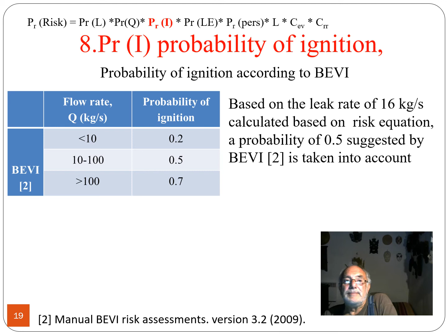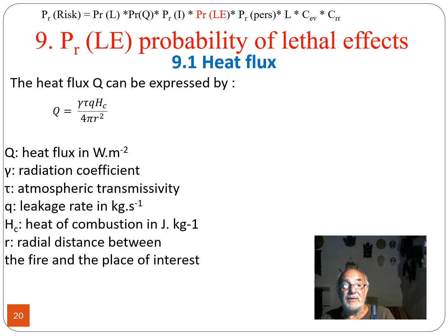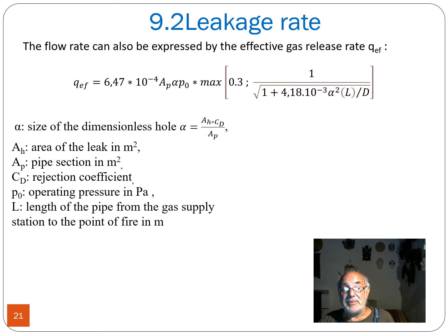The probability of lethal effect can be computed for two situations: heat flux or explosion. The heat flux, capital Q, can be expressed by this formula, where gamma is the radiation coefficient, tau the atmospheric transmittivity, Q the leakage rate, in our case 16 kg per second, H subscript C the heat of combustion, and R the radial distance between the fire and the place of interest. The flow rate can also be expressed by the effective gas release rate, QF, according to this formula. In this formula, alpha is the size of the dimensionless hole, A subscript H is the area of the leak, A subscript P is the pipe section, C is the rejection coefficient, P0 is the operating pressure in Pascal, and length is the length of the pipe from the gas supply station to the point of fire in meters.